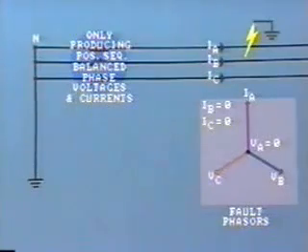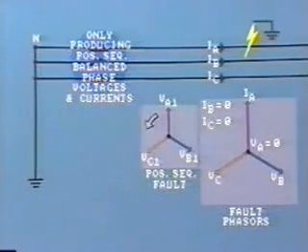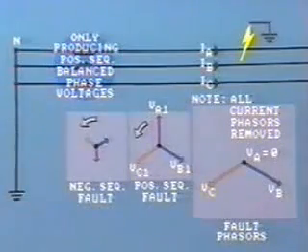Throughout this segment, we're assuming the fault path to consist of resistance only, and the current is therefore in phase with the voltage. The current in lines B and C is zero in both cases, as system load is considered to be zero. Our phasor diagram shows that the system is completely unbalanced. The generator is still producing positive sequence voltages and currents, but at the fault the positive sequence voltages fall to two-thirds of their pre-fault values. Now, remember our previous conclusion — any unbalanced fault has negative sequence components acting on the positive sequence quantities. And where a ground fault is present, we need to add yet another set of components.